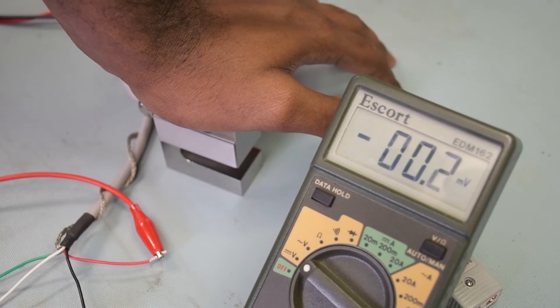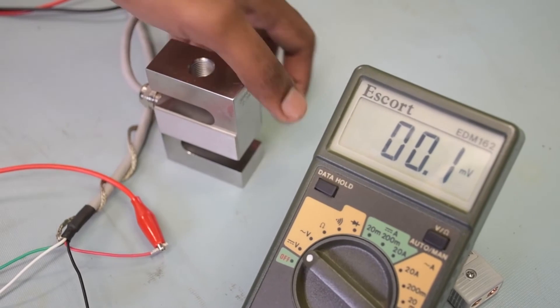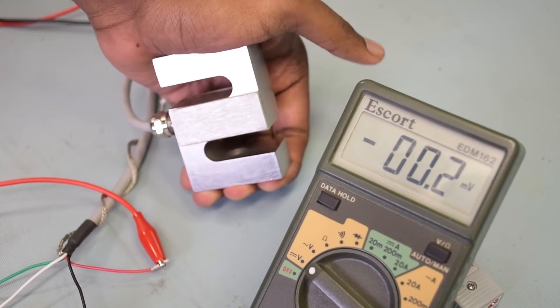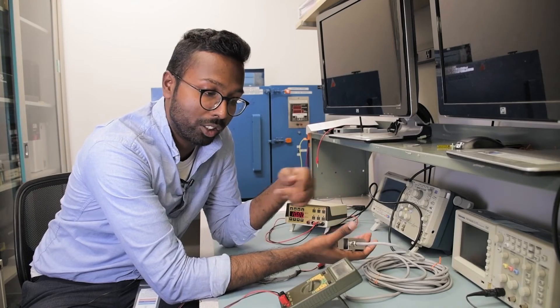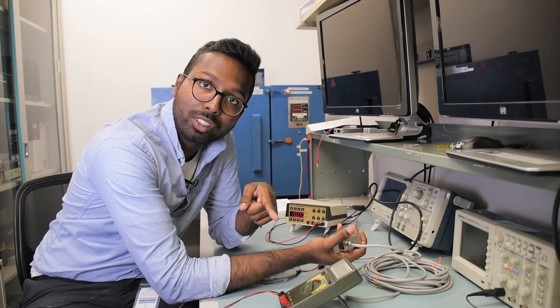Now, if you have a calibrated weight source or a calibrated dead weight of half scale or full scale of the rated capacity of the load cell, you can apply that on the load cell to see if it matches the normalized data that you see on the calibration certificate.